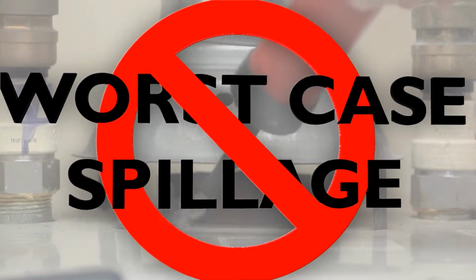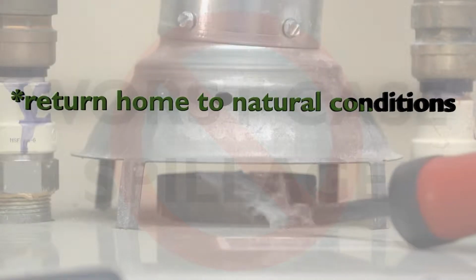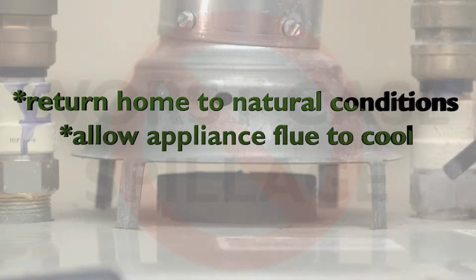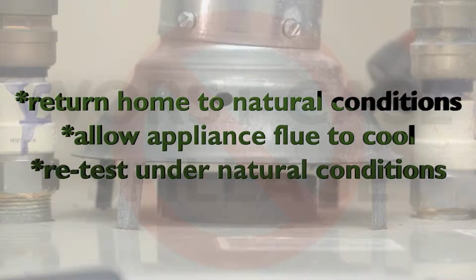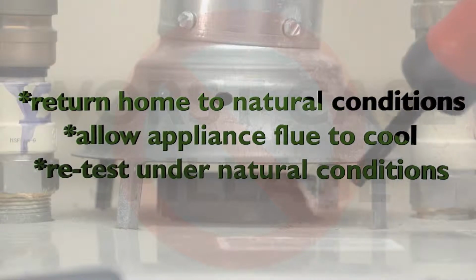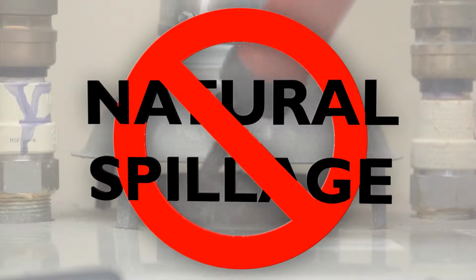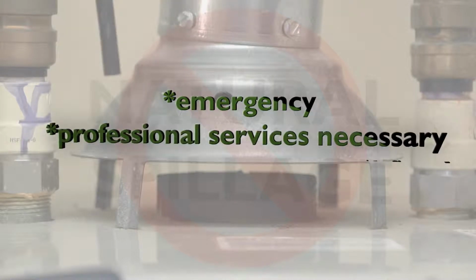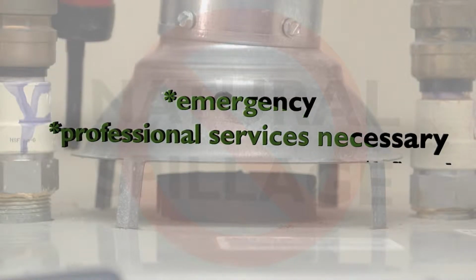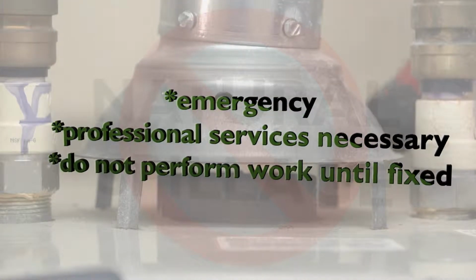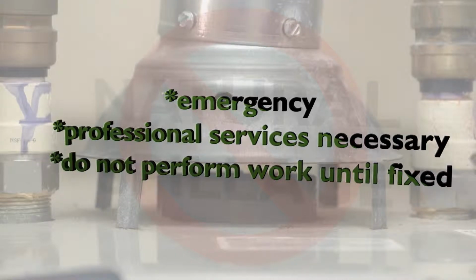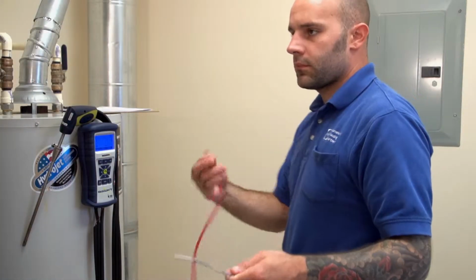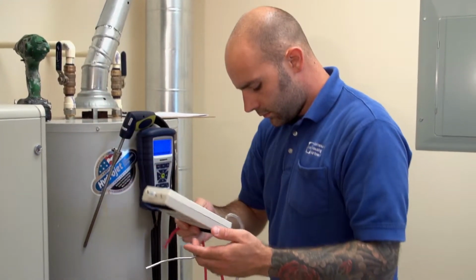If the appliance fails spillage under worst case, return the house to natural conditions, allow the appliance's flue to cool, and retest the appliance under natural conditions. If it fails under natural conditions, it's an emergency and needs to be serviced by a professional immediately. No weatherization work may be performed until this problem has been corrected. If spillage passes, continue with recording the draft measurement.